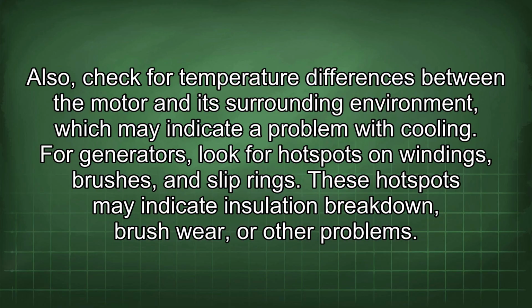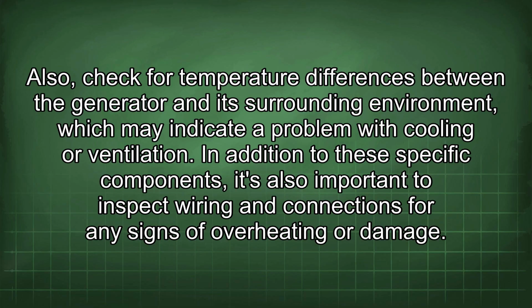For generators, look for hotspots on windings, brushes, and slip rings. These hotspots may indicate insulation breakdown, brush wear, or other problems. Also, check for temperature differences between the generator and its surrounding environment, which may indicate a problem with cooling or ventilation.